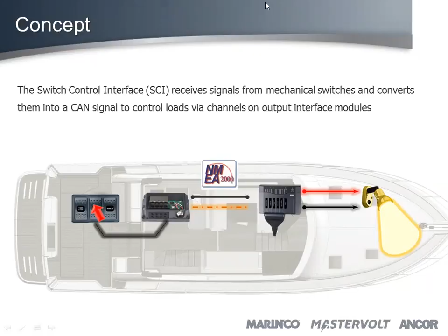It seems like a nightmare to diagnose if there's a fault. Where before you might have a fuse or circuit breaker, now you have a processor, digital management, NMEA. Yeah, we have processes to troubleshoot that. It sounds complicated. No, it's not that complicated, and I'll show you in a second why there's redundancy here too. First of all, you can always plug in a laptop and monitor the network and see if the actual contactor is giving that signal. That's number one, the number two I'll come into in a minute.